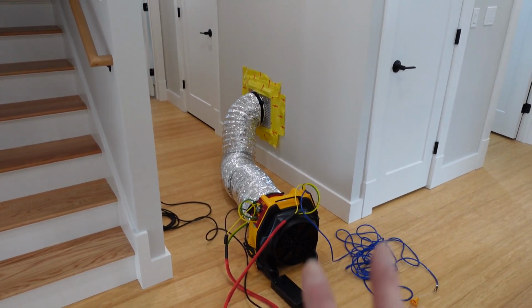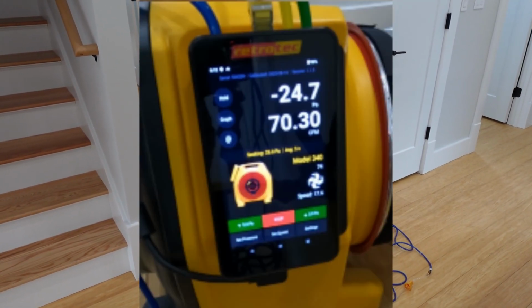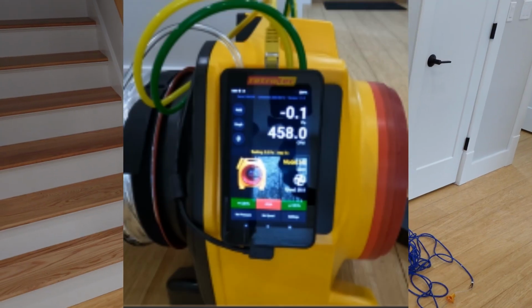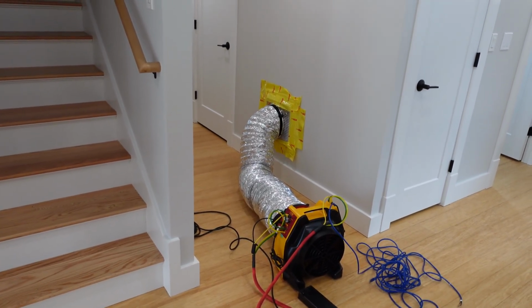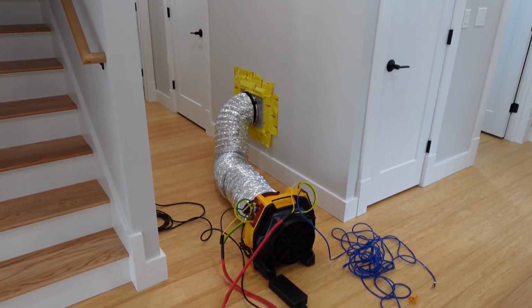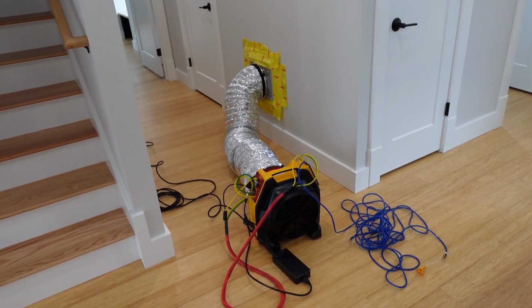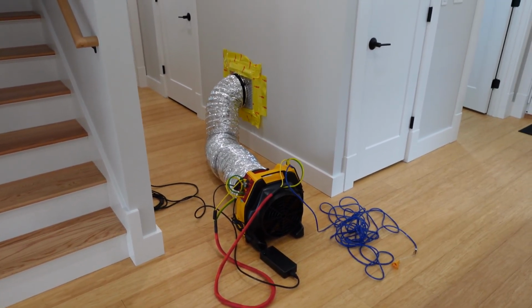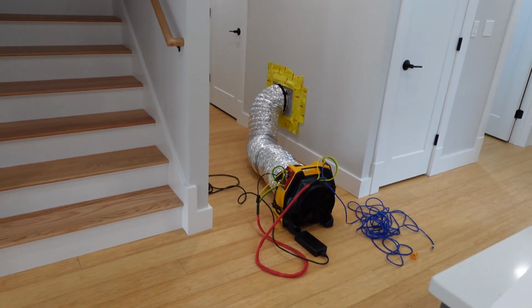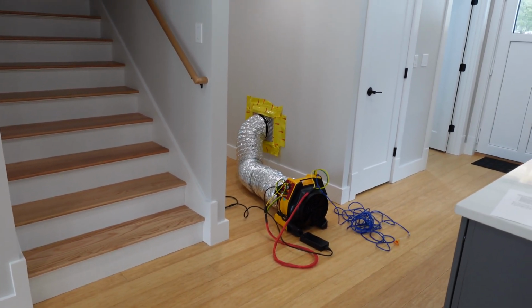All right, so we ran two tests. We ran a duct leakage test and a total system airflow test. The duct leakage test is going to tell us the integrity of the piping system to ensure that it is going to provide proper airflow. The total system airflow test is confirming that the amount of airflow we're looking for is actually being achieved.